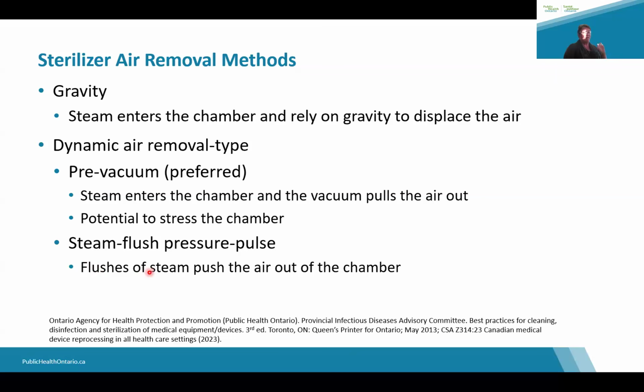Oh my God, this one. Steam flush pressure pulse autoclave, which uses controlled pressurizations and flushes of steam. So there's no vacuum here. What it does is it pulses the steam into the chamber to push the air out. And so the chamber never drops below atmospheric pressure. Therefore, there's no need to conduct a Bowie-Dick test daily, because the chamber is always at a pressure greater than that of the ambient air. So you're not going to get a leak through your chamber. But for steam flush pressure pulse autoclaves, there is an alternate method for evaluating the efficacy of air removal, and for that you should follow your manufacturer's instructions for use. And so that's it for the 3 different types of autoclaves.